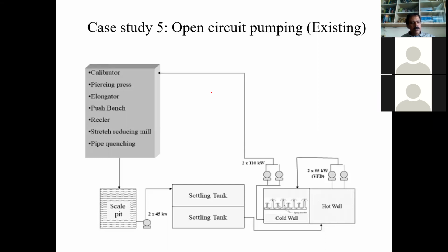And this is a case of an open circuit pump in a steel rolling mill, where we have cooling water directly in contact with the output material. Initially the ingots are punched; there's a calibrator, a piercing press, an elongator. It goes through several processes and needs to be cooled. The bearings and the rollers all need to be cooled, which means the water is in direct contact with all these materials. So the direct contact water has a lot of iron particles. It comes into the scale pit. From here you pump the water using two pumps of 45 kilowatt.